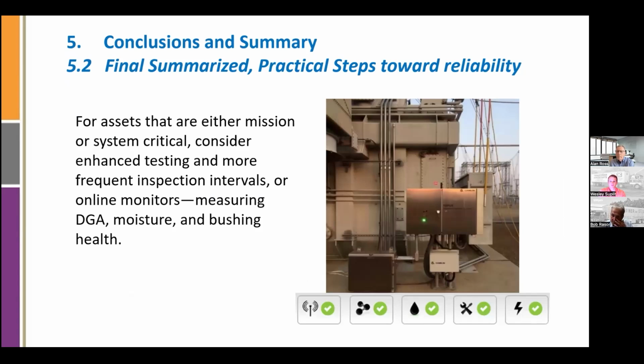For larger transformers, especially if they have any kind of a gassing tendency, there are some pretty efficient, accurate online monitors now that can connect directly to dashboards, and you can look at the data in real time. They can include bushing monitoring as well as the main tank. You can do some PD work, looking for partial discharge in the tank with the bushing monitoring.